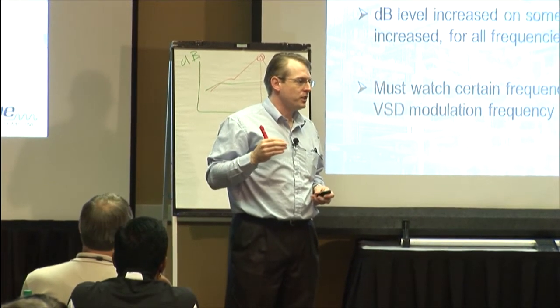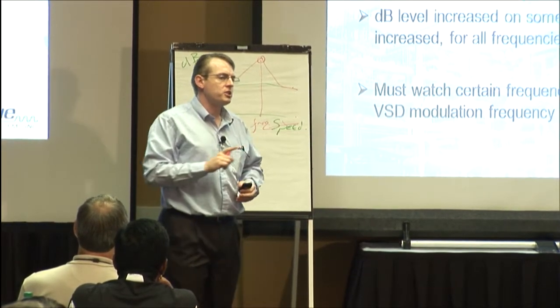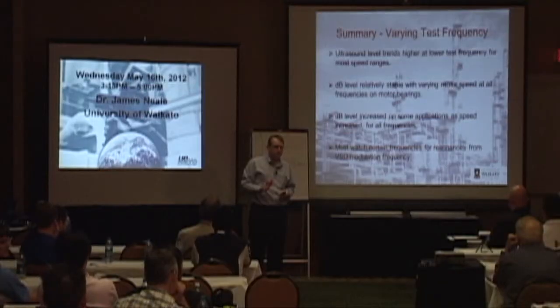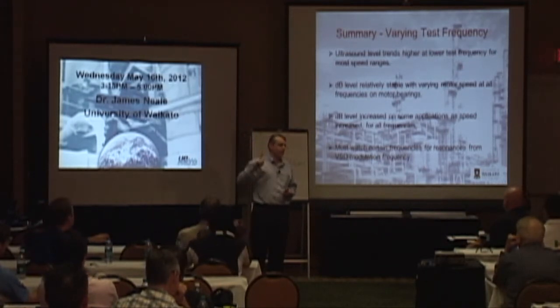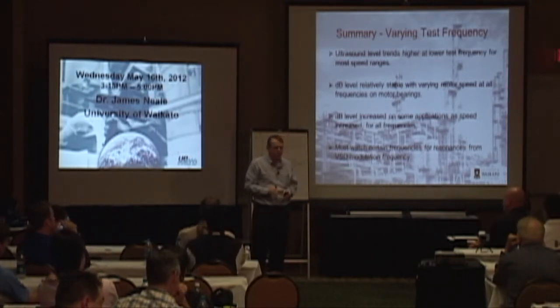Obviously, when you couple that with whatever the unit's doing with speed and everything else, you need to be prepared to recognize it. I'm not recommending you change the modulation frequency of the VSD, because that could be set for other reasons. It's simply a matter of saying, hey, we don't have to use a set frequency for every bearing.